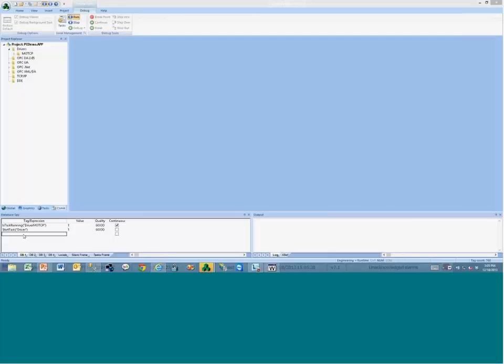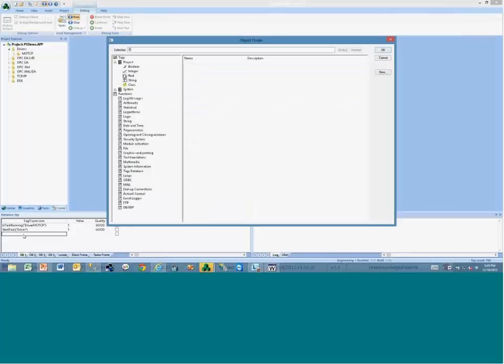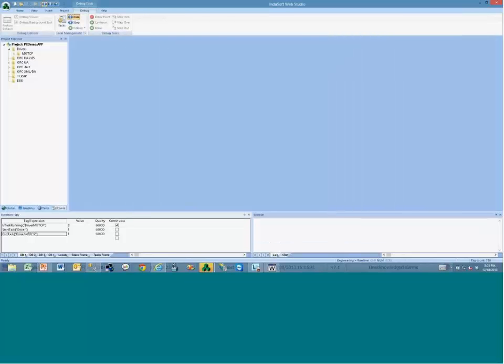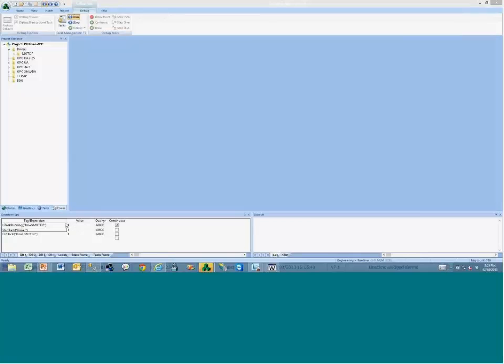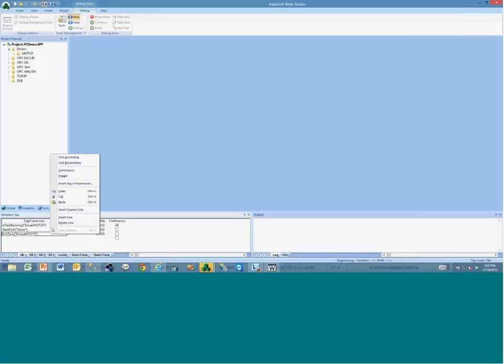If I want to stop one particular driver, I can use the function end task, and again use the syntax driver and the name of the driver that I want to shut down. As you see here, when I execute the end task, the driver is no longer running. And if I execute the start task, the driver runs, and end task stops the driver.